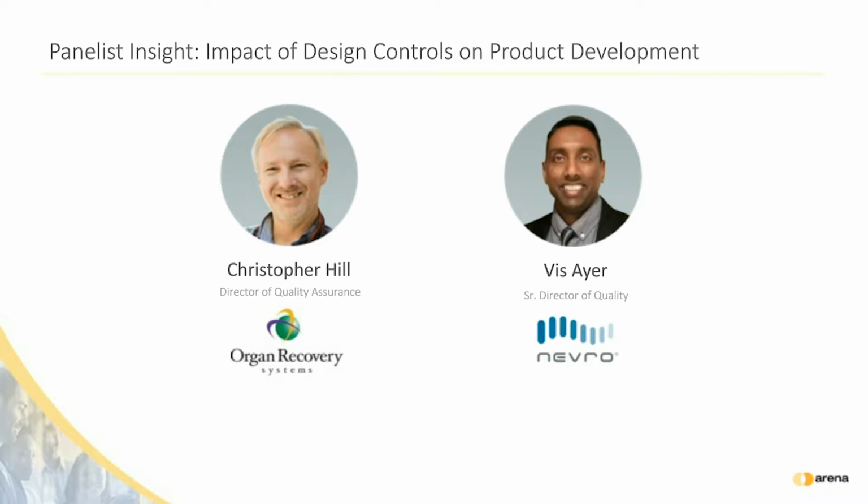Sure. But before we talk about the challenges, I did want to reiterate one point from what Ann described. The FDA design controls are required, and it's something that we all have to comply with. But it's also good business practice in planning your project, identifying data sources, deliverables, responsibilities, and risks. Those are all good steps for any product launch, whether it's a regulated device or not. So we don't just follow the best practices because we want to avoid the 483s. We follow them because we want our final products to be well-designed, well-controlled, and well-documented.